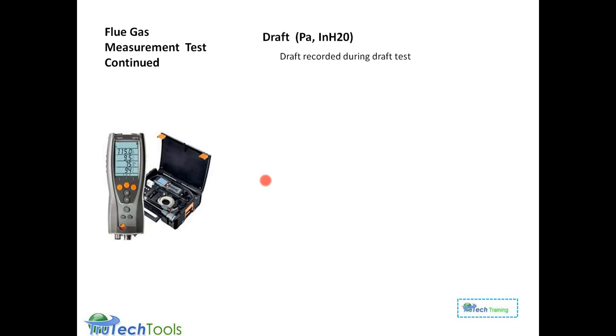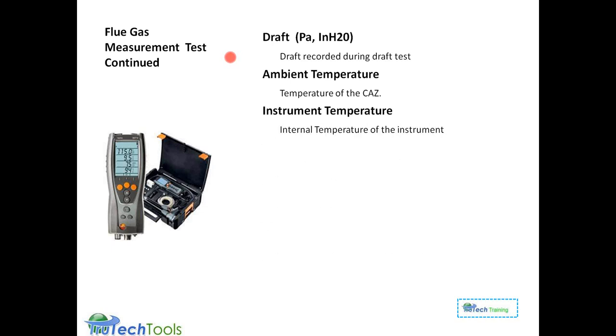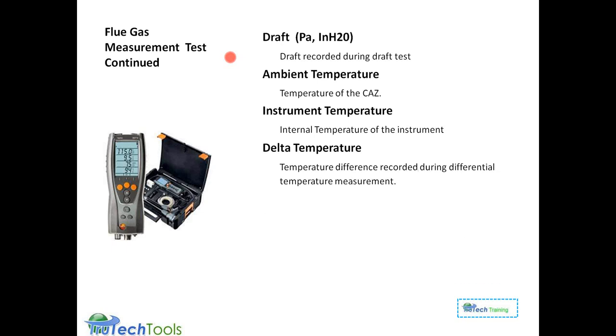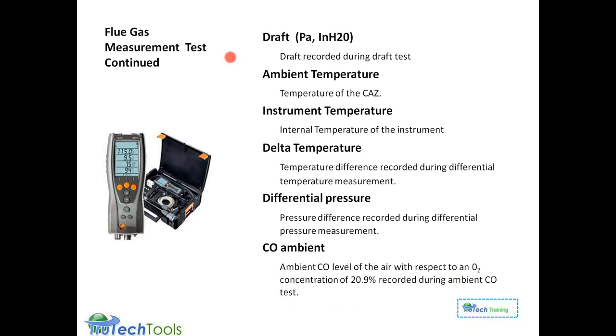So some of the other parameters we'll talk about that were inside that list of parameters you can set up: the draft reading, the ambient temperature reading, which is the temperature of the combustion air zone, the air going into combustion, the internal temperature of the instrument, the differential temperature between the two temperature probes, differential pressure between the two pressure ports, and the CO ambient, which is the level of CO measured in the air directly.